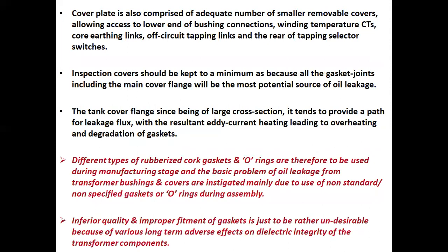The cover plate also comprises an adequate number of small removable covers allowing access to the lower end of bushing connections, winding temperature sensors, core earthing links, off-circuit tapping links, and the rear of tapping selector switches. Inspection covers should be kept to a minimum because all the gasket joints, including the main cover flange, are the most potential source of oil leakage. The tank cover flange, being of large cross section, tends to provide a path for leakage flux, with the resultant eddy current heating leading to overheating and degradation of gaskets.